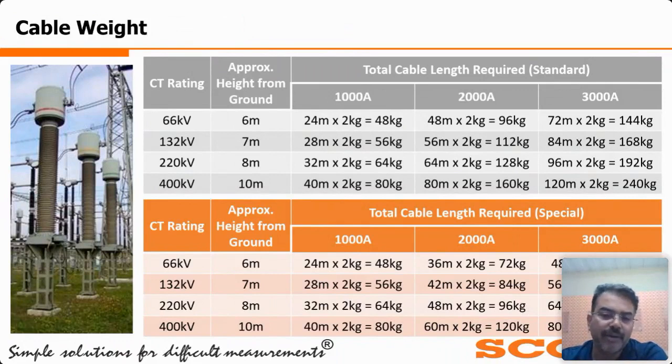So theoretically, we can go up to 960 ampere with a 120 square mm cable. To be very frank, we are not using 120 square mm; 120 is the industry standard, and we are using 125 square mm. With that, we are reaching up to 550 as a continuous rating. Continuous means really continuous, and for a short time it is around 10 to 15 minutes. Hope I could clear your doubt, sir.